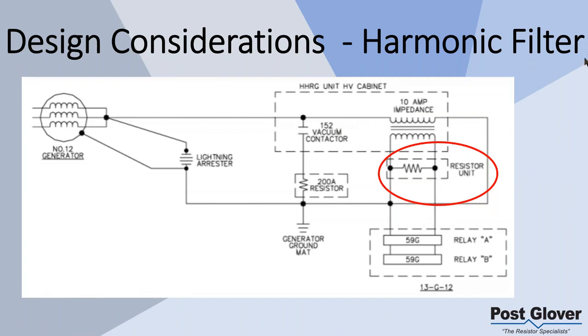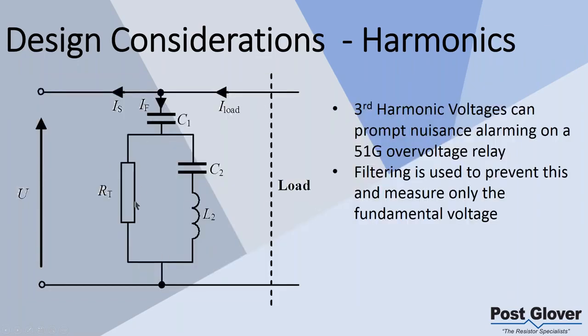Another thing to consider is harmonic filtering. It doesn't actually matter where you have this. What you're doing here is trying to have accurate information for your relays and your controls. If you have third harmonics, which typically the third harmonic voltage is present, you can create some with the generator. Essentially, you're going to need some kind of a filter here, whether it be a high pass filter or whatever it's going to be, to be able to get rid of those third harmonic voltages, so you're tripping or alarming properly.